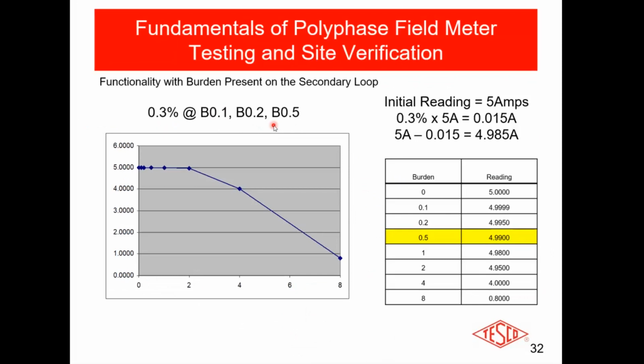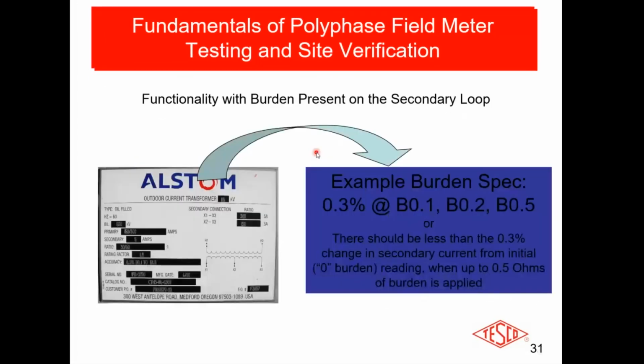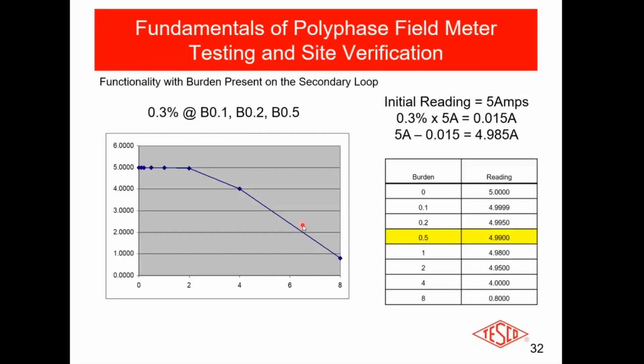You've probably heard, sometimes for whatever reason you cannot keep the CTs close to the meter. Sometimes there are logistical reasons why you just can't do it. Well, as soon as you exceed a certain distance, you probably all have seen where you have certain guidelines that say, oh, if you're going to go further than 5 feet away, now you have to increase the size of the wire. Why are you increasing the size of the wire? You're increasing the size of the wire to reduce the resistance in that wire, reduce the burden. And you've got to reduce the burden because on that faceplate it says, hey guys, you can't go more than here, otherwise we're going to start losing accuracy.